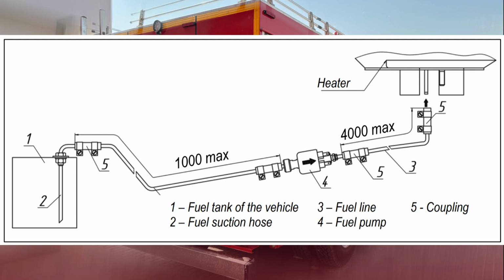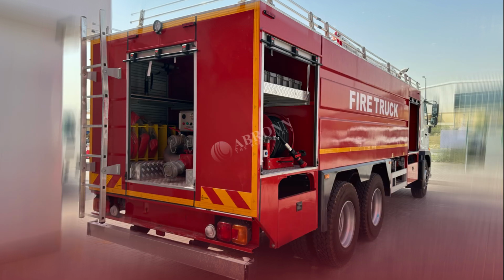The fuel line system should be as short as possible. The recommended maximum length of the fuel line is 5 meters. The distance between the fuel tank and the fuel pump should not exceed 1 meter, and the distance between the fuel pump and the heater should not exceed 4 meters, as shown in Figure 18 and Figure 21. Before installing a fuel suction hose in the fuel tank of the vehicle or vessel, make sure that the fuel level is high enough to ensure operation of the heater and low enough to easily remove the fuel tank if needed.